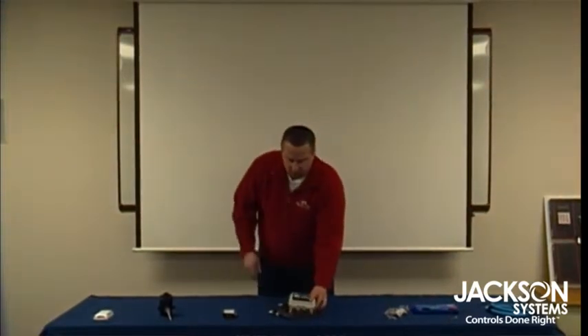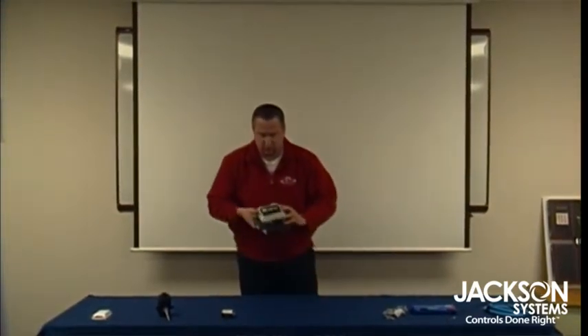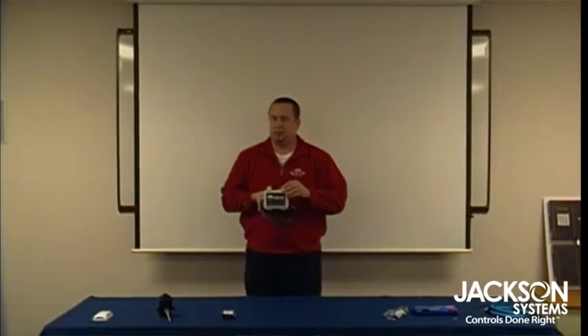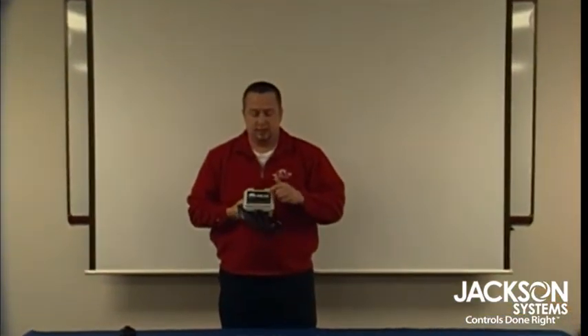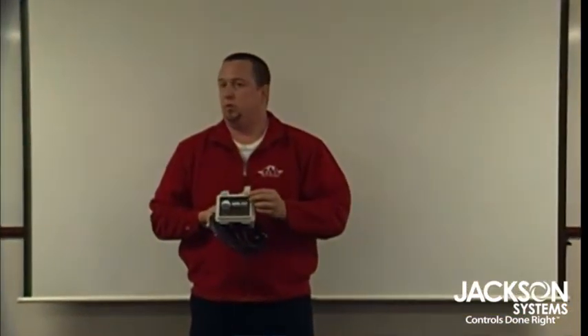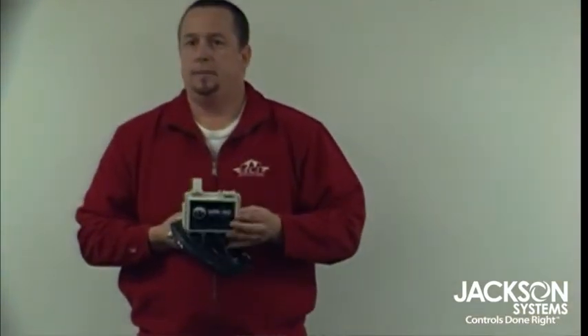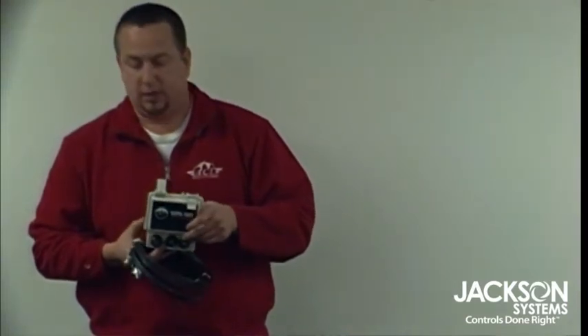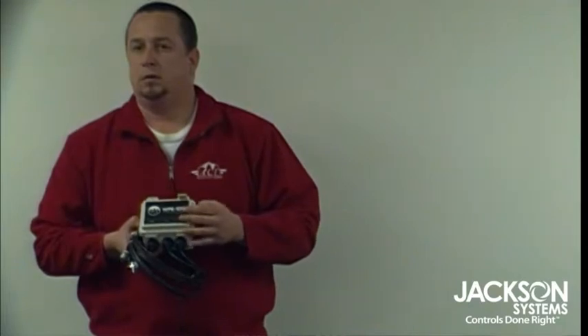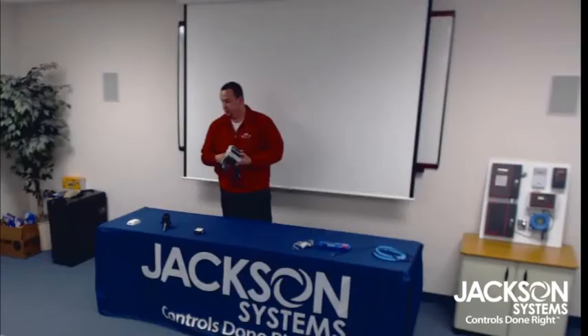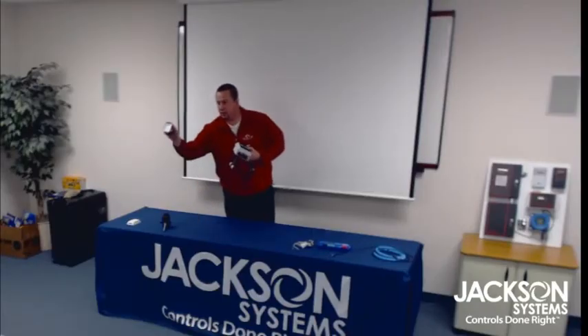We're manufacturing a wet-to-wet differential pressure transmitter now too. It's called our WPR series. This is the Dash 100, so this one simply goes up to 100 PSI. And it's jumper selectable pressure ranges. Do you have anything in the lower range? This will jumper select all the way down to, I believe, 10 PSI. Smaller, lower static pressure? Yes. For air, right? Yep, I'll be covering that next.